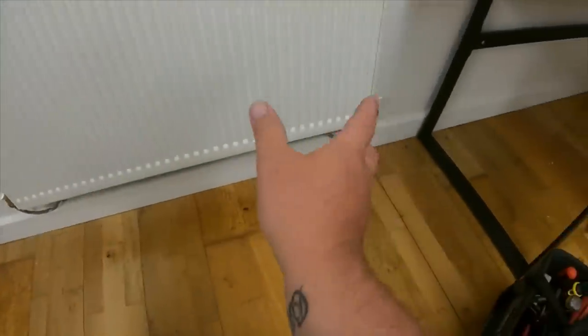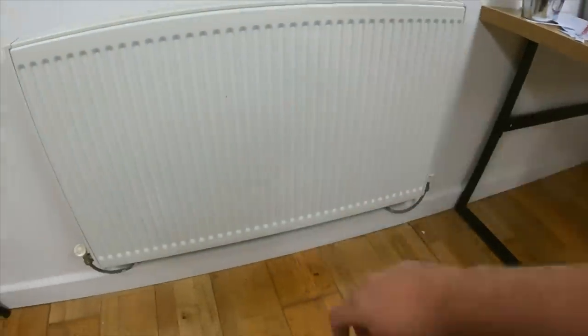Right, let's get on with the video. We'll start from the basement and work our way up. First issue: this radiator is on two lockshield valves and the customer says it's just red hot all the time, which it's going to be with the valves open. There's no thermostatic control. I'll put it to the landlord if he wants a TRV fitted — though on a three to four storey building you'd have to drain the whole system down to change that lockshield. We've turned it off and let it cool down.